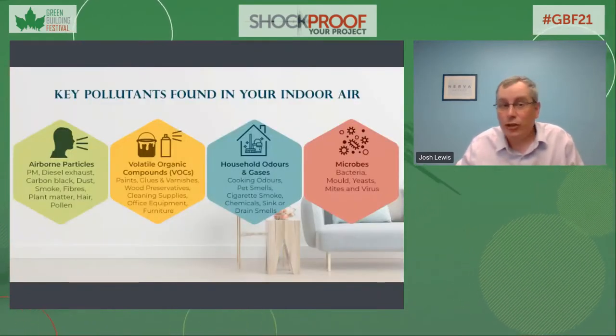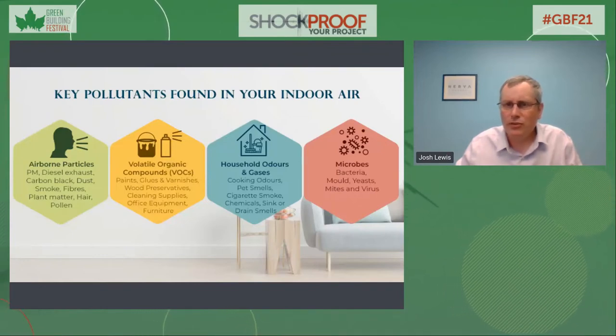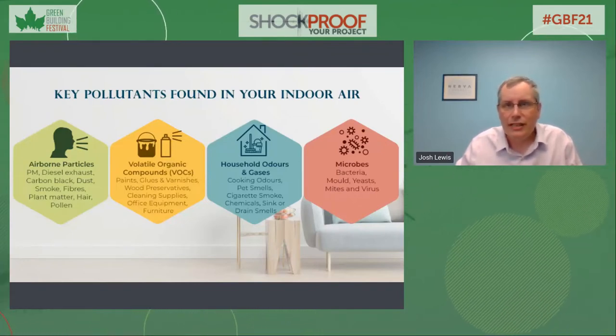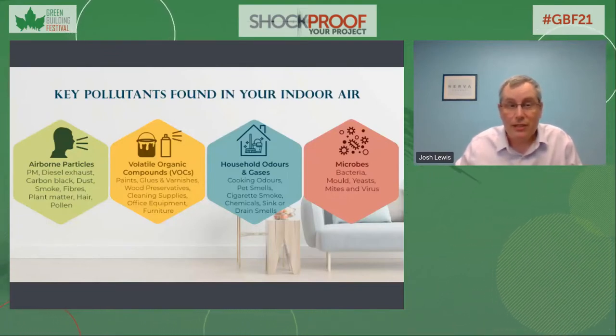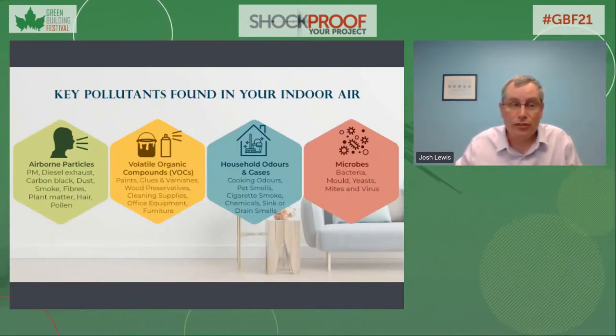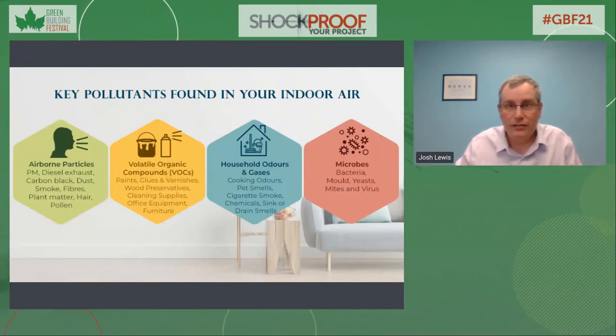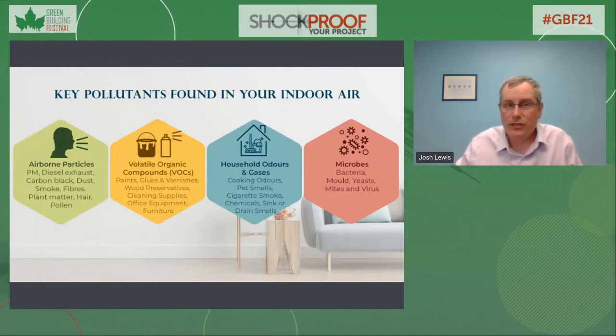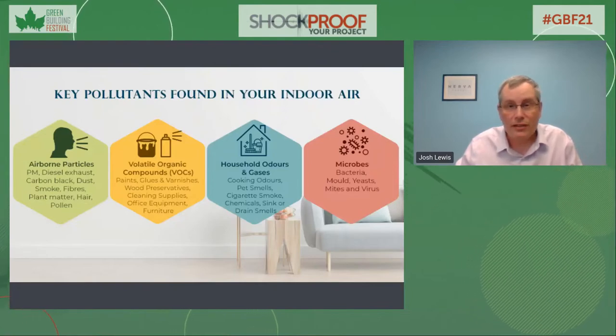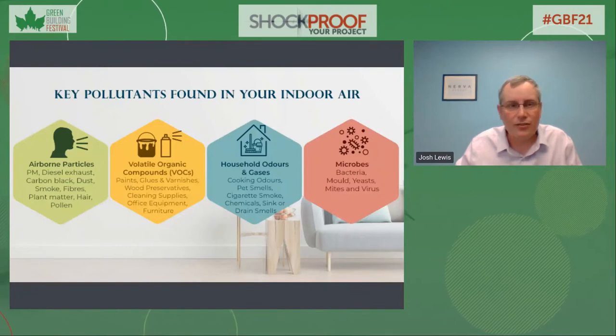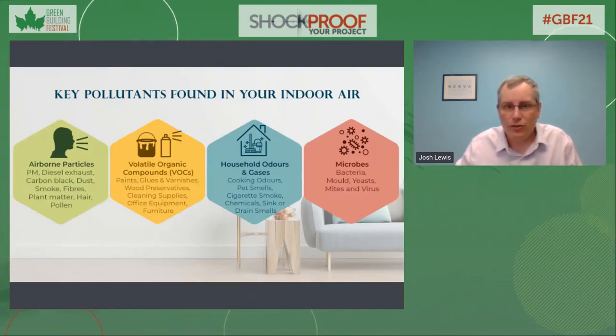COVID-19 has been a trigger to force us to rethink what HVAC systems should do. Allowing ourselves to fall into the IAQ trap is no longer acceptable. We need to effectively remove contaminants out of the air through a proper mix of filtration, dilution, purification, and humidity. The benefits will extend well beyond the current situation we find ourselves in, including reducing the risk of spread of seasonal flus, colds, and other airborne pathogens, while also reducing the concentrations of allergens as well as VOCs that are inevitably generated due to the materials we use for construction inside buildings.